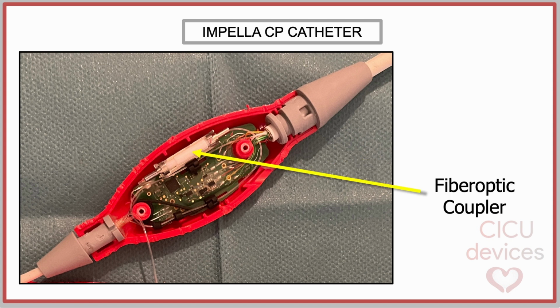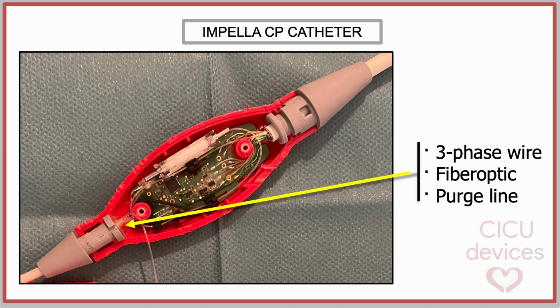exchanged. In addition, a fiber optic coupler can be identified within the red hub. This element provides the interface between two fiber optic cables, maintaining precise optical continuity and secure transmission of signals critical to device performance. Finally, at the distal end, we can find the purge line, power wires, and optical fiber entering into the catheter, completing the transition from the hub to the intravascular portion of the system.